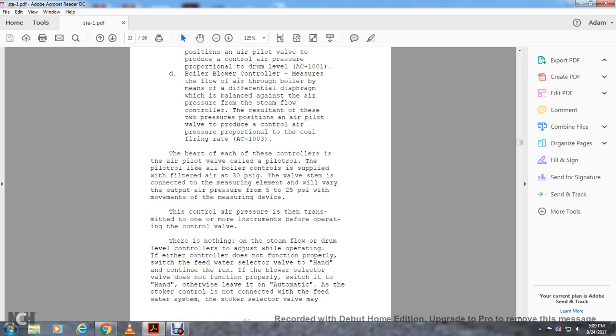pilotrol. Pilotrol, like all boiler controls, is supplied with filtered air at 30 psi gauge, and the valve connects with the measuring element. It will vary the output air pressure from 5 to 25 psi with the movements of the measuring device. This control air pressure is then transmitted to one or more instruments before operating the control valve. There's nothing on the steam flow for the drum level.